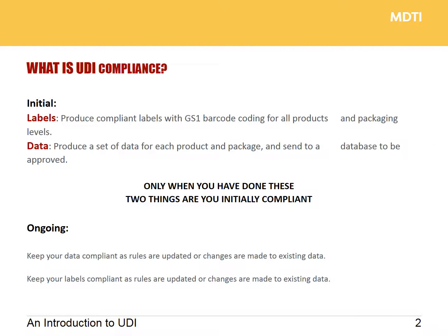So if we start off with what is UDI compliance — just to clarify, it's compliant labels with GS1 barcoding for all products and packaging levels, produce a set of data for each product and package and then send that data to a national database to be approved. Once you've done those two things you've achieved compliance. Ongoing, it's keeping the data compliant as rules are changed or you change your data, and keeping your labels compliant as rules are updated or you make changes to your existing data.